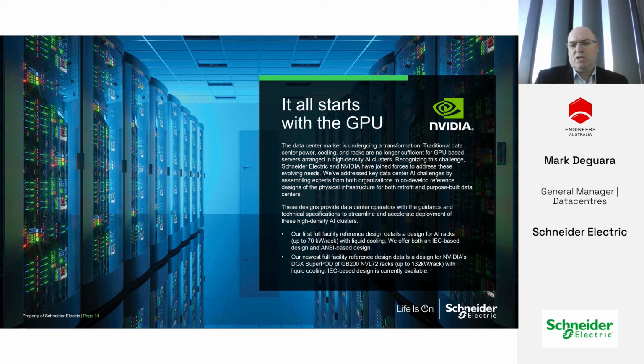So what is happening in the GPU? I'm using NVIDIA here as an example, but if we looked at a reference design that we built about 18 months ago, we came out with a reference design that was designed for 70 kilowatts a rack. Now, we released another reference design only 12 months later, so around 3 months ago, at 132 kilowatts a rack. And this has been driven by the GPU. This has been driven by what's happening, in this case NVIDIA, driving what's happening at the server level and ultimately what happens at the rack level.